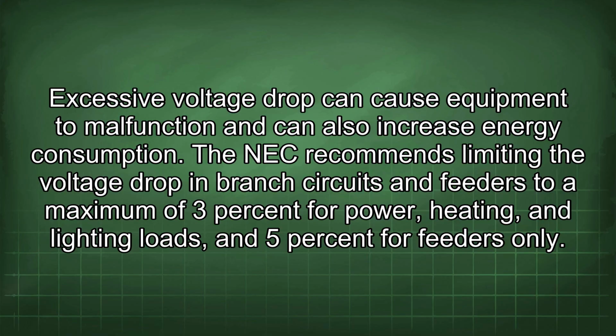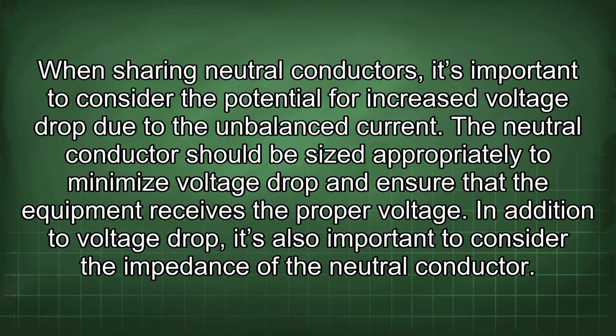The NEC recommends limiting the voltage drop in branch circuits and feeders to a maximum of 3% for power, heating, and lighting loads, and 5% for feeders only. When sharing neutral conductors, it's important to consider the potential for increased voltage drop due to the unbalanced current. The neutral conductor should be sized appropriately to minimize voltage drop and ensure that the equipment receives the proper voltage.